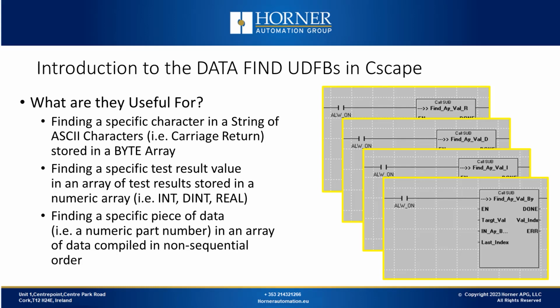They have a variety of different uses. This sort of data find is useful if you're looking for a specific character in a string of ASCII characters. For example, ASCII characters are most often represented as a byte array, and each character is a byte long. And you may have an application where you're looking to extract an important piece of data from a string of ASCII characters that may be coming in from a barcode reader, let's say a carriage return character. And it's important for you to know where that carriage return is located in the string as you extract the piece of information you're looking for from that barcode. This data find function would allow you to search for a carriage return in that byte array and tell you that location.